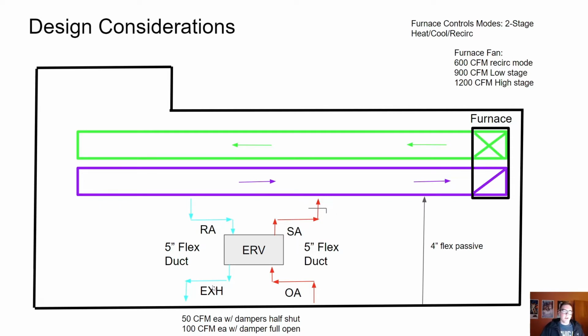So when I show you this design, I can go into balancing it as well and the importance of balancing it. But what I found is on my system with the dampers half closed, I'm getting about 50 cubic feet per minute when the ERV is on, and then with the dampers full open, I'm getting about 100 cubic feet per minute, right, 100 cubic feet going that way, 100 cubic feet per minute going this way.